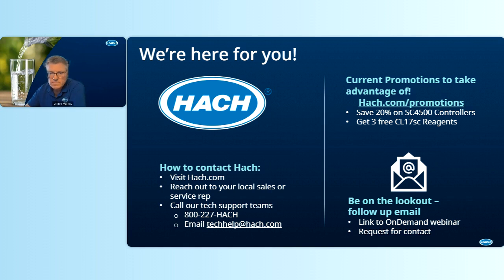Great, thank you. Another one that just came in is, which analyzer to use when chlorine concentration is 200 ppm? Well, I can take that one. Nobody has, say, a colorimetric option for this high chlorine concentration. Amperometric options are available. However, as Terry said, and we said in this presentation, the calibration will be an issue. So this application is very difficult. It's like a stormwater application with a blast of chlorine, and we are aware of these applications.